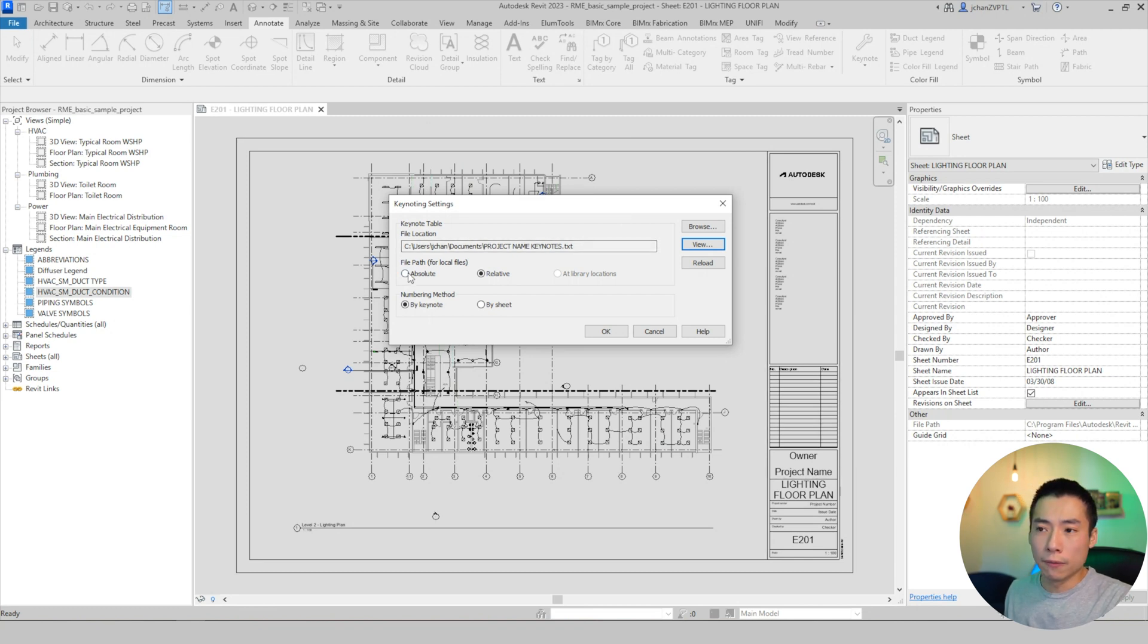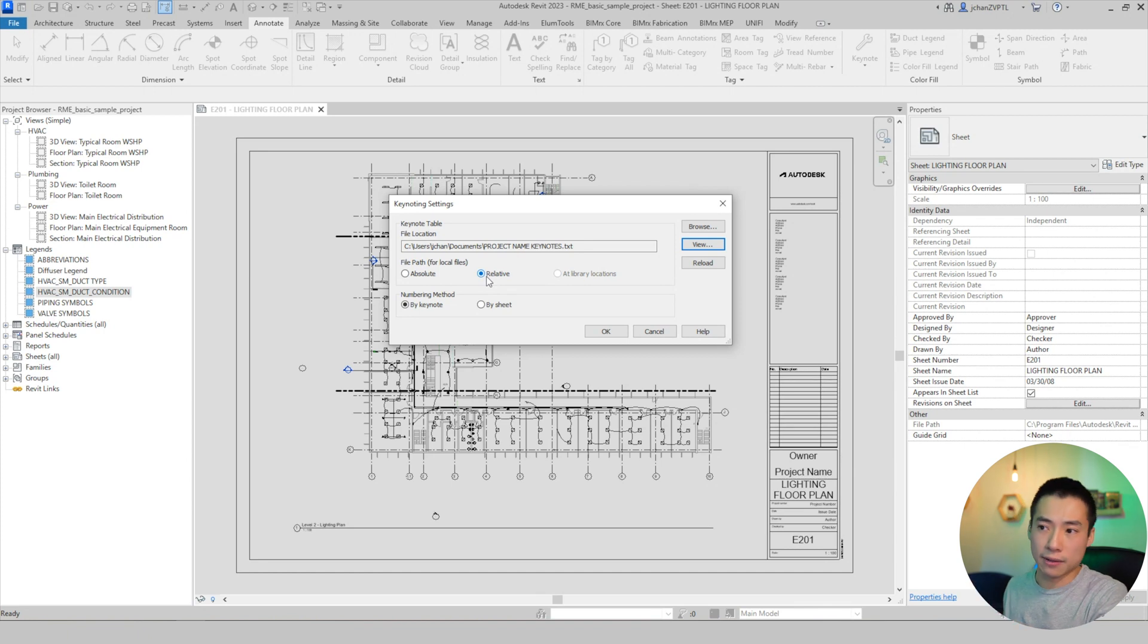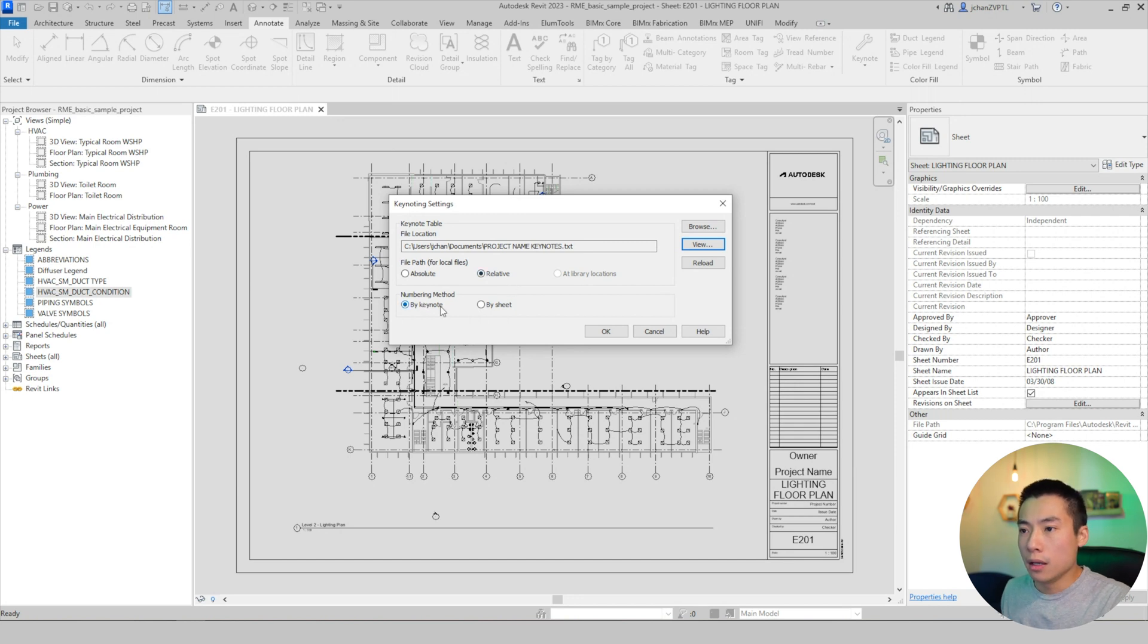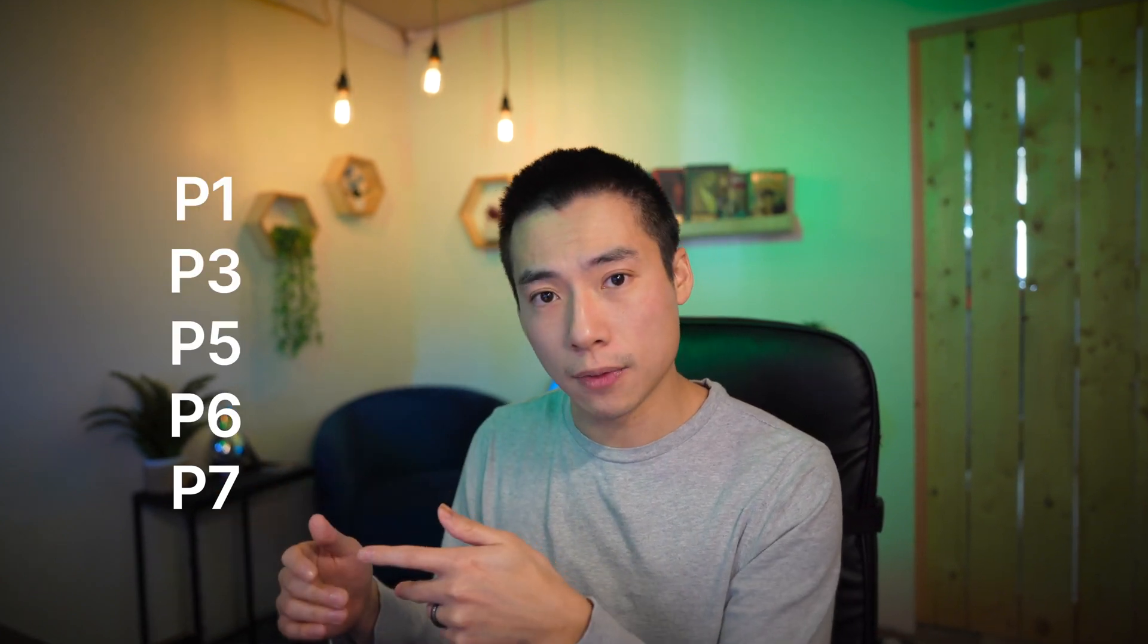Now over here for file pathing, I always like to hit relative, just in case if you ever move the whole project, then updating one will be able to fix the rest. Like if you update Revit's pathing to find the other Revit links, this will update as well. Numbering method is where you can have a little creativity or make it match your company standard. If your numbering method is by keynote, then what you type into the note field, like P1, L1, P2, that's exactly what shows up on the floor plan and on your drawing. It won't get renumbered if you skip every other number. Like say you want to use note one and three, but you don't need to, your drawing will actually just say P1 and P3. It won't skip over that and just make it sequential.